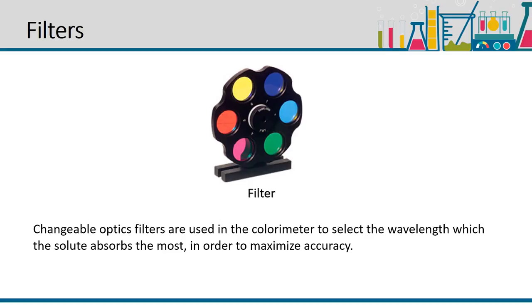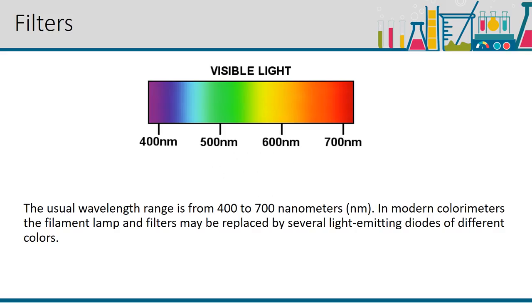Changeable optics filters are used in the colorimeter to select the wavelength which the solute absorbs the most in order to maximize accuracy. The usual wavelength ranges from 400 to 700 nanometers. In modern colorimeters, the filament lamp and filters may be replaced by several light emitting diodes of different colors.